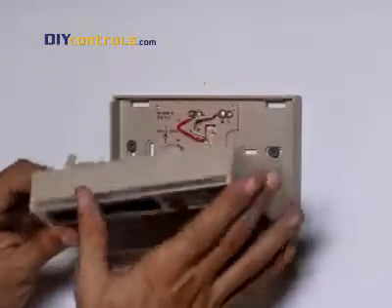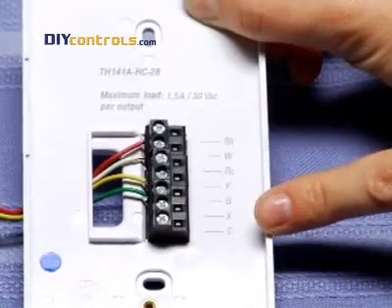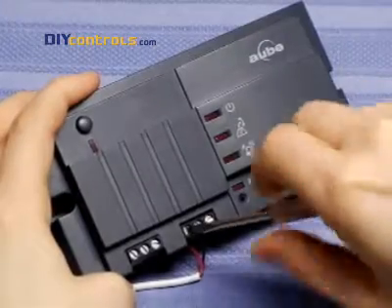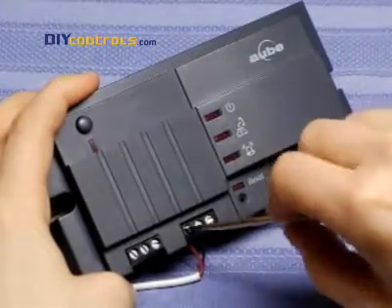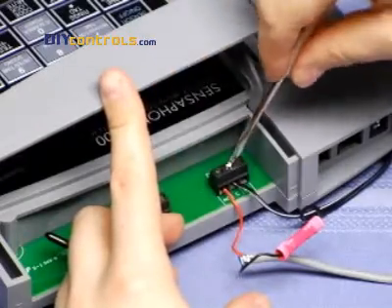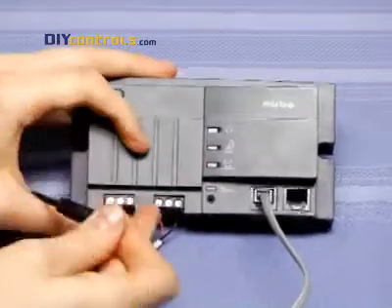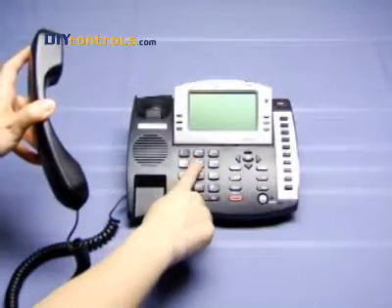Visit our remote thermostat control tutorial for a helpful chart. To install, first swap out your existing thermostat for the phone-controlled one. The new thermostat will have two additional terminals that the old one didn't have. Wire these terminals to the CT241 or Sensaphone. With Sensaphone, you may need to wire in a 12-volt transformer as well. Check our tutorial for details. Then hook up the CT241 or Sensaphone to a dial tone and power it up.